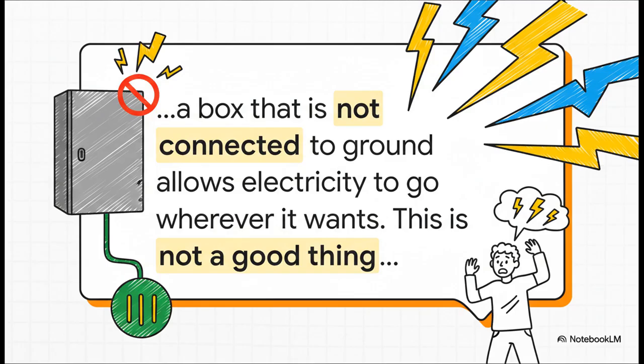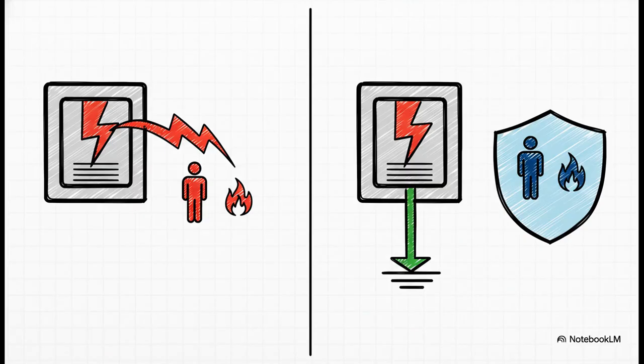It's incredibly dangerous. This is why having a metal box is so important. Grounding connects that metal box directly to the earth with a wire, so if there's ever a short circuit or a power surge, all that dangerous stray electricity has a super easy, safe path to follow right into the ground, instead of, say, through a person or into something that could start a fire. It's the ultimate electrical escape route.